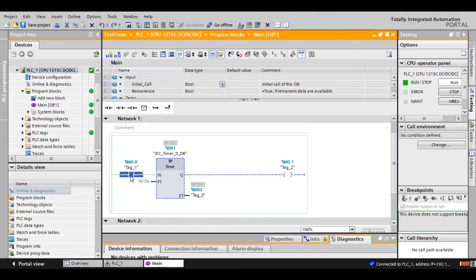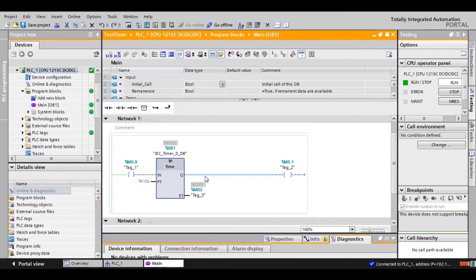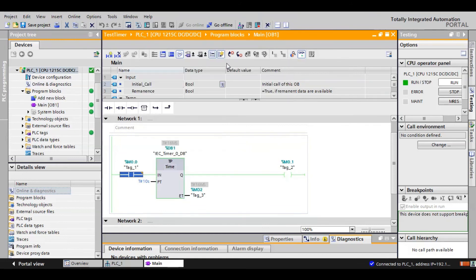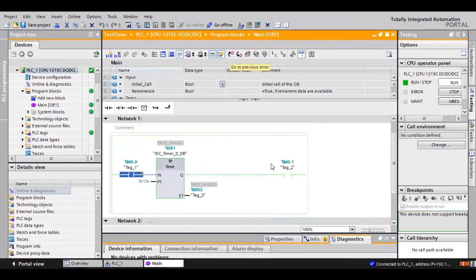Now let's verify the third condition: when the output is high and the timer is running, if the input goes from 1 to 0, what happens to the output? Let's modify to 1 and then immediately modify to 0. As you can see, the output does not go to 0 when the input goes to 0 — it waits until the timer finishes. This confirms the working principle of this TP timer.